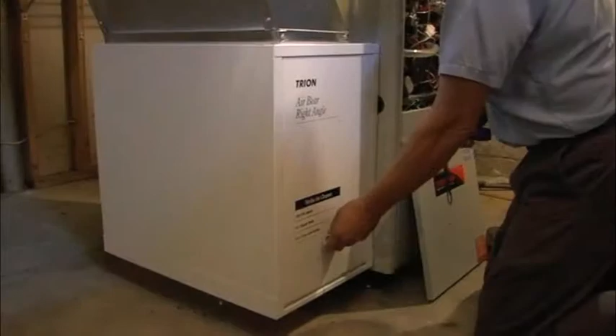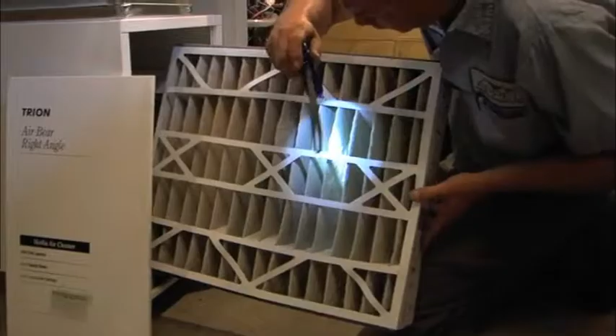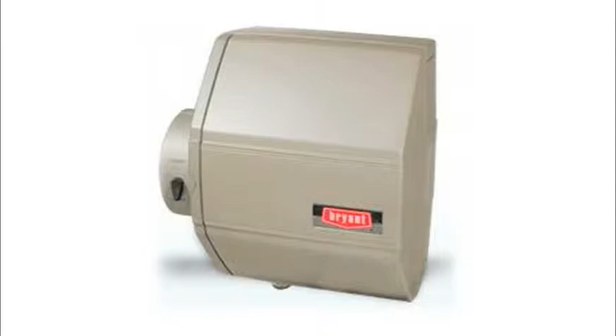We'll also need to check the filter, make sure it is clean. A lot of people use the 4-inch thick medias, which can last 6 to 12 months. We recommend them for their effectiveness and lack of airflow restriction. If your system has a humidifier, we'll want to maintain that as well. We do all this just to make sure that you don't have a failure in between our visits. And our experience shows that during a cold snap, most of the calls we get are from people who don't have us maintain their equipment annually.